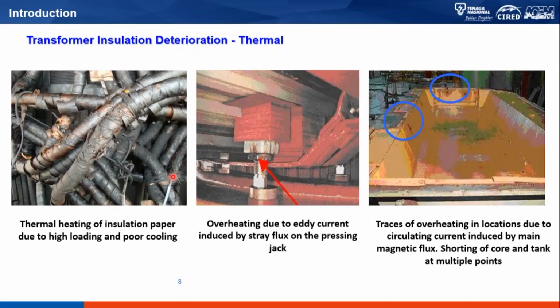As you can see on the screen right now are some of the effects of thermal stress on the transformers. Some of the transformers finally fail, but not because of the thermal stress. Of course, the final failure would be from the electrical side due to flashover and so on.